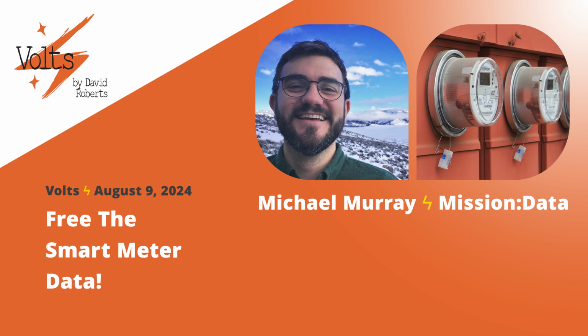The new smart meters, version 2.0 you might say, have Wi-Fi on board. And the major meter manufacturers in North America have, I would say, largely standardized around a certain application protocol over Wi-Fi called IEEE 2030.5. You might know that as a smart inverter standard. California and other states require that for communicating with inverters. It's possible to send real-time, meaning once-a-second, usage data over Wi-Fi.